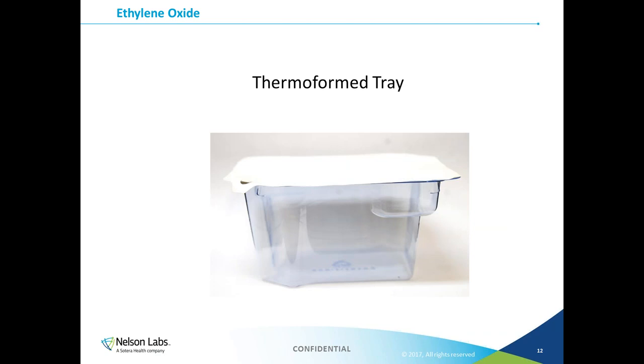Finally, here is another very common style: the breathable tray, again using spun-bound HDPE or medical-grade paper. These are used to constrain heavier, bulkier, or odd-shaped items. This is also a good design option if you have sharp or pointy features that would more easily puncture a pouch. The tray can be formed to snugly restrain the medical device while the filter material provides very good breathability.